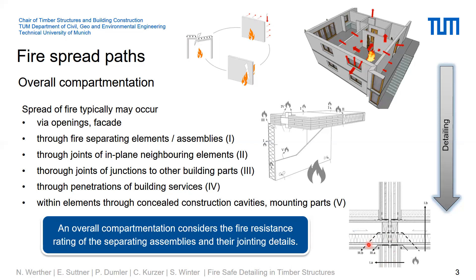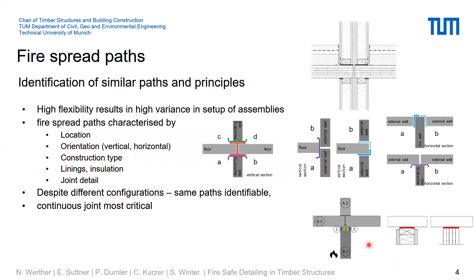An overall compartmentalization considers the fire resistance rating of the separating element and also the jointing details. As we started the project, we did a review of typical construction details and typical construction systems in timber structures to get an overview of what is needed and what must be covered by design principles. Based on this review, it became obvious that the location, the presence of lining and insulation products, all influence fire spread.